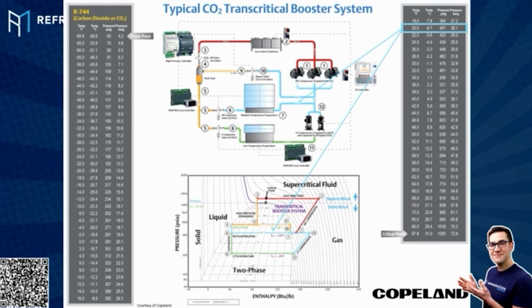And then we have another pressure in the system. So our medium temp suction. So this one here, for an example, is 407 psi or 28 bar. And then lastly would be the low temp suction, minus 4 or 271 psi. So the thing is that you got to think about this just a little bit different.